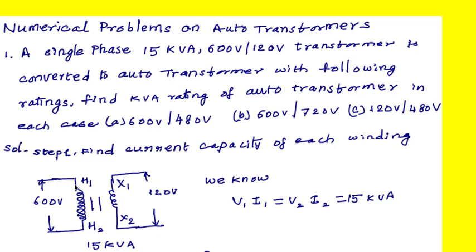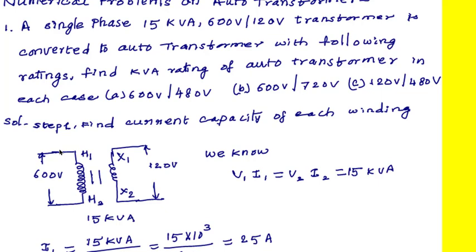First, find the maximum current capacity of the 600-volt winding. The current flowing in the primary winding is I1, and the applied voltage is V1. So I1 = kVA rating ÷ V1 = 15 kVA ÷ 600 = 15×10³ ÷ 600 = 25 amperes. This high-voltage 600-volt winding can carry a maximum of 25 amperes.